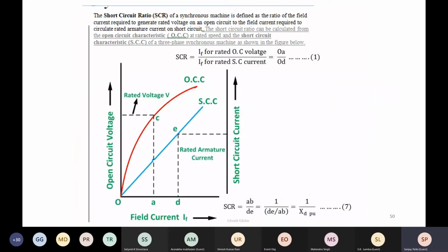Okay, before we come to load angle, I will explain the other parameter, which is called the open circuit characteristic and short circuit characteristic of the machine. Basically, this open circuit characteristic is the excitation field current required for the open circuit voltage to get generated, and this is a voltage versus field current curve. This is the OCC, which all of you must be familiar with.